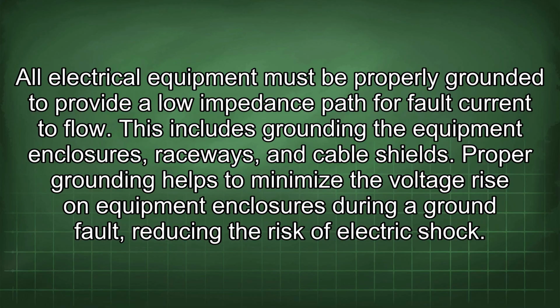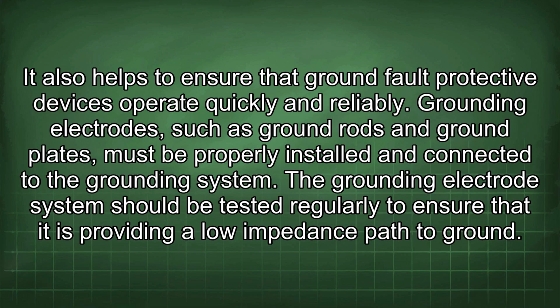This includes grounding the equipment enclosures, raceways, and cable shields. Proper grounding helps to minimize the voltage rise on equipment enclosures during a ground fault, reducing the risk of electric shock. It also helps to ensure that ground fault protective devices operate quickly and reliably.